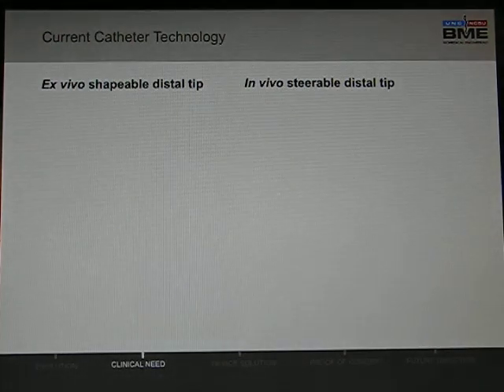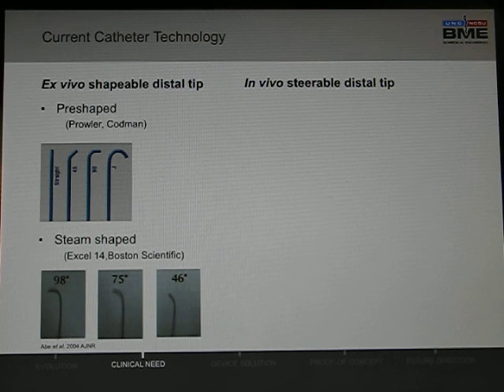With current catheter technology, we have the ex vivo shapeable, where the distal tip can be shaped outside the patient, or the in vivo steerable. The ex vivo shapeable comes pre-shaped like these that can be chosen at the discretion of the interventionalist. If these do not meet their needs, the distal tip can be steam-shaped to various orientations. These series of images show the catheter tip loses its original orientation once inserted coaxially through a larger diameter catheter, and even more so once a wire is passed through and manipulated.